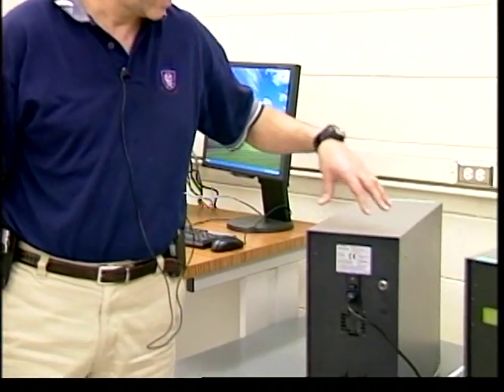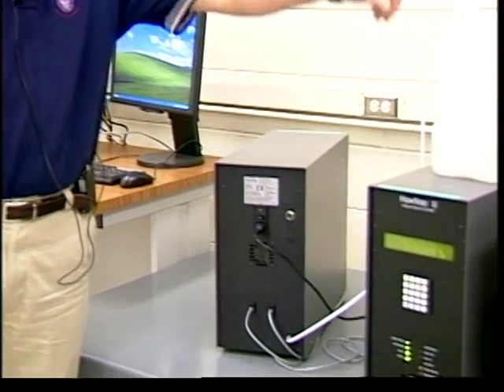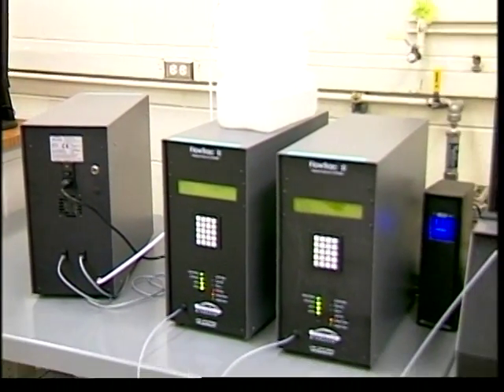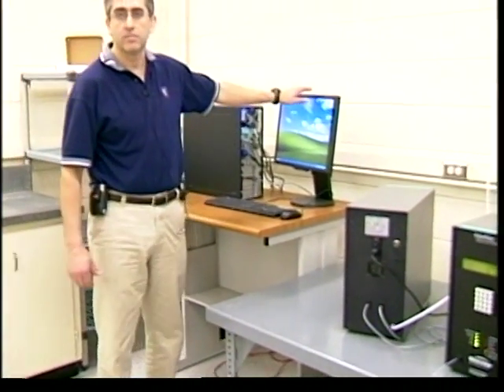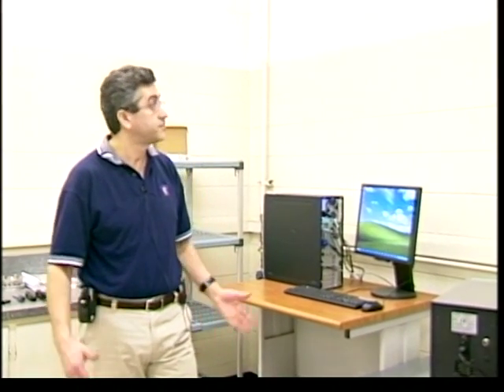In addition to giving you a backup time, it gives you protection for any instability in the power supply or brownouts or things like that. So it's a good thing to have. Always, as I said, I highly recommend using a UPS. Now, you get the power cord that goes from the back of all these units connected to the UPS, and also you have a computer and a monitor. The monitor does not have to be in the UPS. It could be running the tests without a monitor. Doesn't make it too fun, but you could.